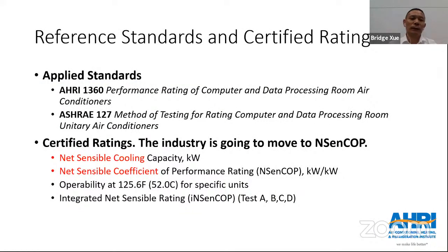So you can see here, the other standard, ASHRAE 127, will be applied for the air code unit. I'm highlighting the net sensible cooling capacity and the efficiency here in my presentation, because today most of the countries talk about total capacity, but when you look at the requirement from a data center, they may talk about dry cooling capacity. So we need to change our mindset to certify new ratings, which are net sensible cooling capacity and efficiency.